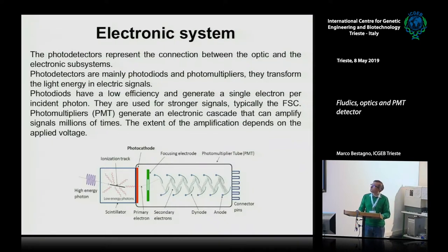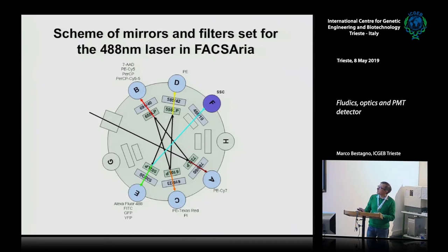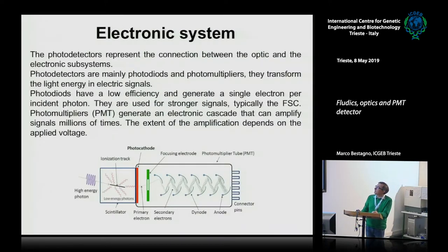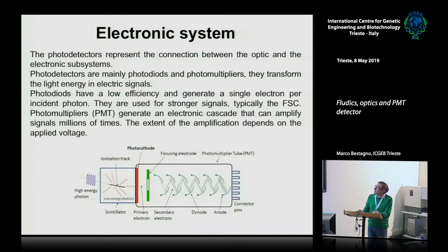Now we come to the electronic system. After separating light and sending it to the appropriate detectors, these detectors transform incident light into electric signals. They are mainly of two categories: photodiodes and photomultipliers. Photodiodes are the most simple, have low efficiency, generate a single electron per incident photon, and are used for stronger signals — typically the forward scatter. Photomultipliers, more importantly, generate an electronic cascade that can amplify the signal up to millions of times.